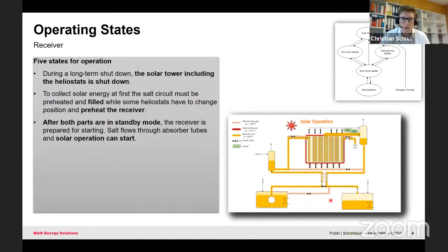So now some words to the receiver itself. Here you see a picture of the receiver. The heat duty was already mentioned. So we have 700 megawatts of thermal power. The mean heat flux density is at around 540 kilowatts per square meter. We have an irradiated length of 23 meters. And the diameter is around about 19 meters.